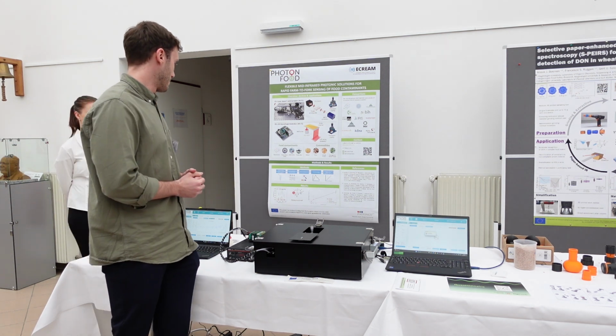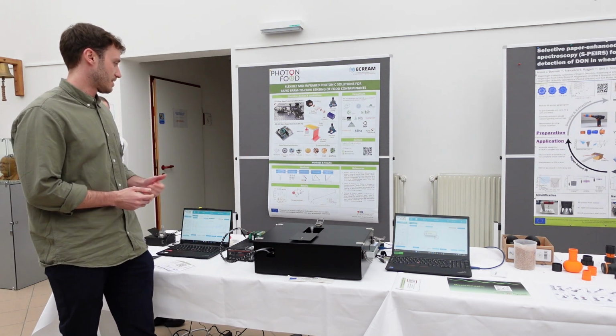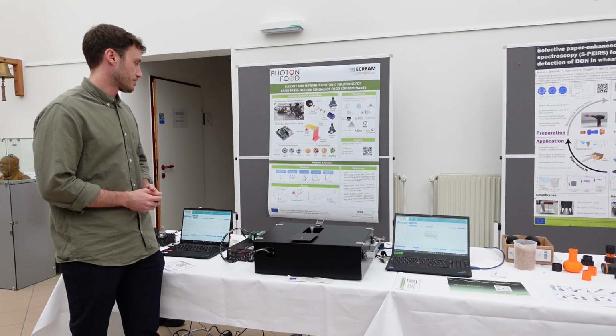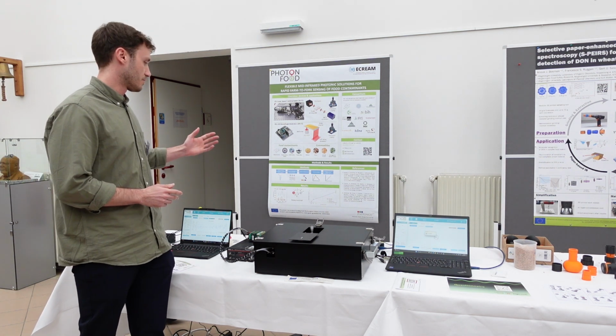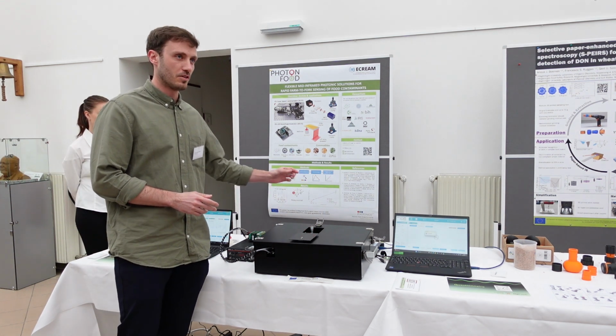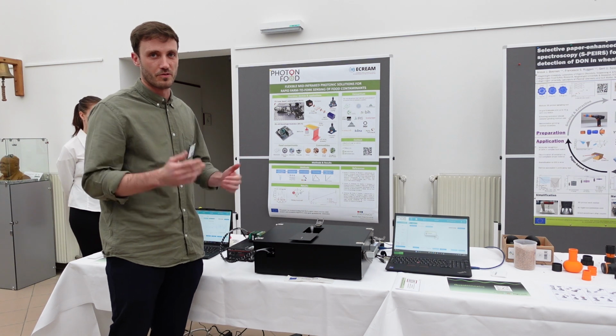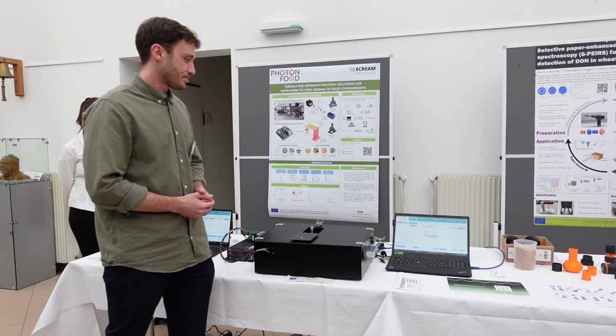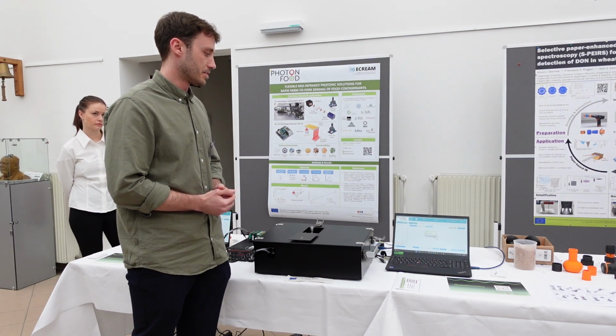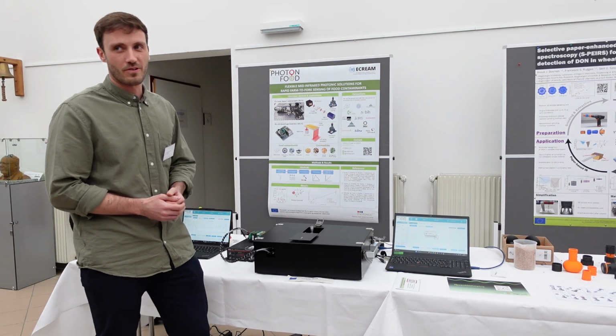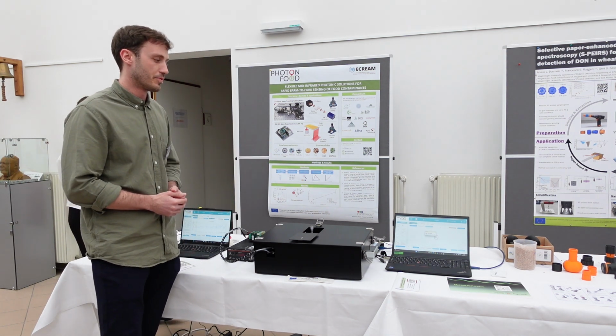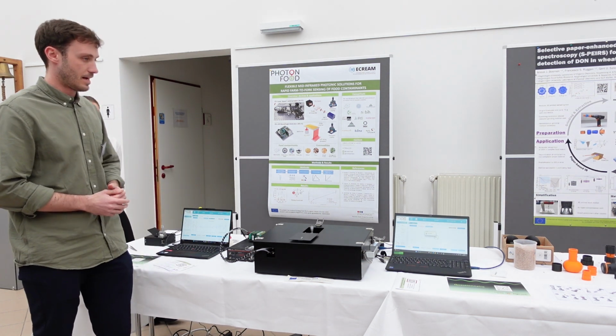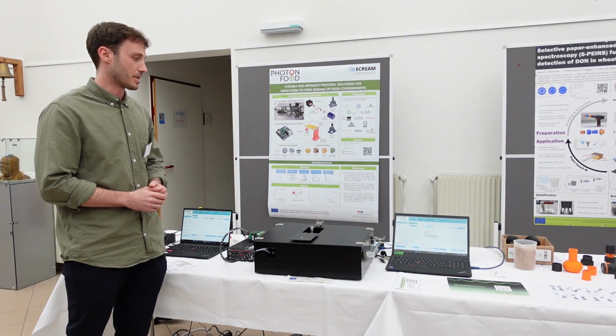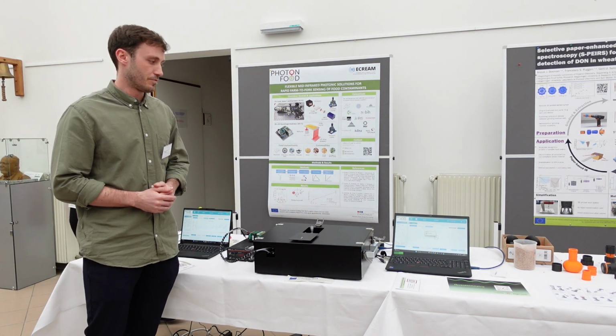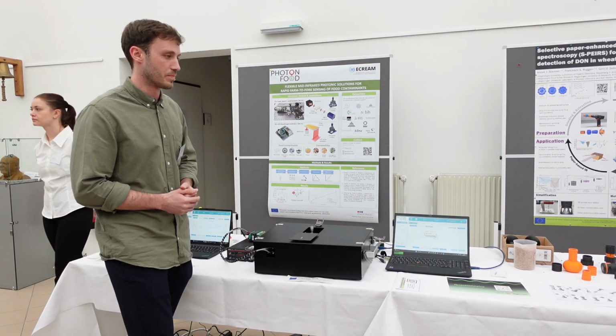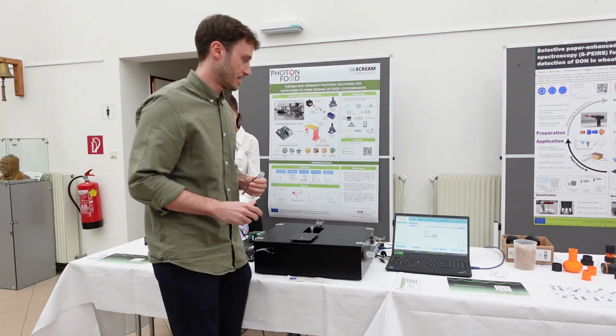Just to mention, as Paulina presented before, we also developed calibration curves not only for paper but also for liquid samples. So this pressure stamp can also be removed and you can place liquid samples or films. We need to wait a bit for the background to be measured. This is more for high fidelity, so the result it brings will not only focus on screening, like the MiFi, which is more intended as a screening method, but also on confirmatory analysis with direct DON quantification with preconcentration.